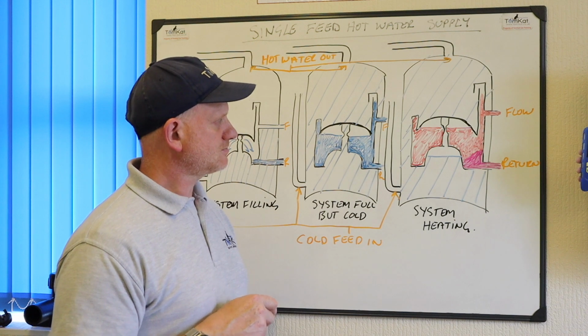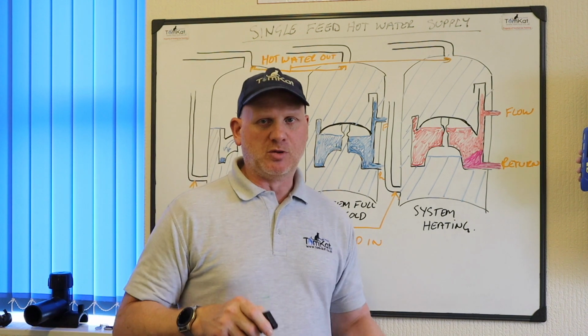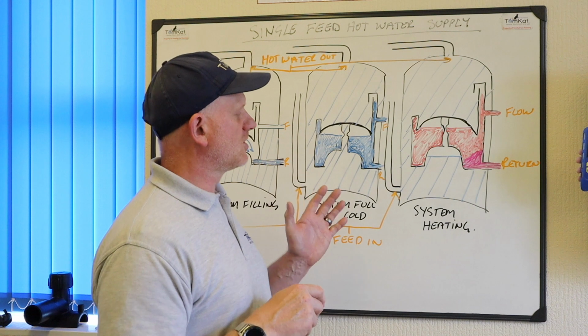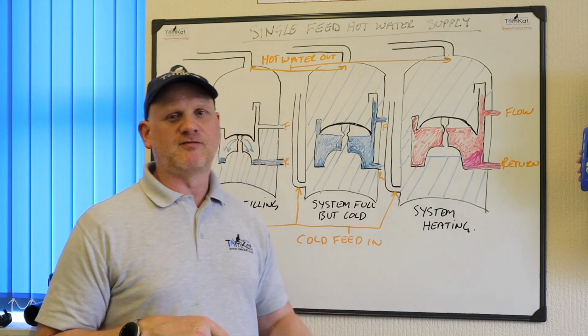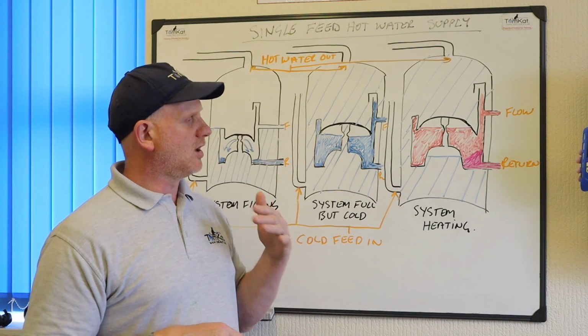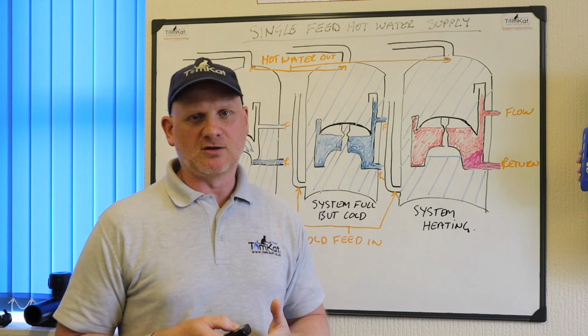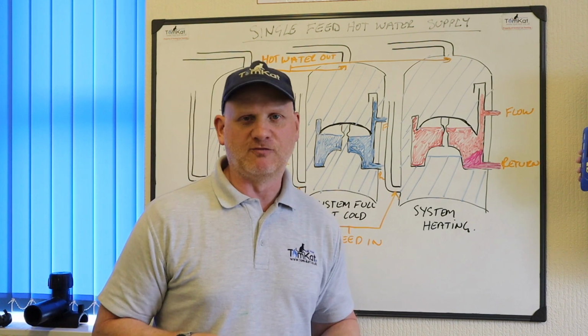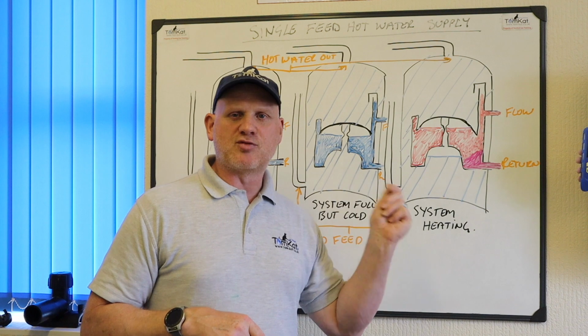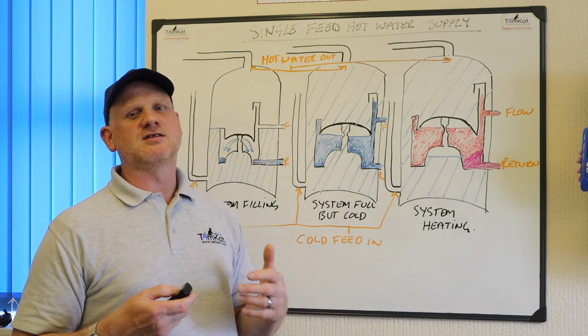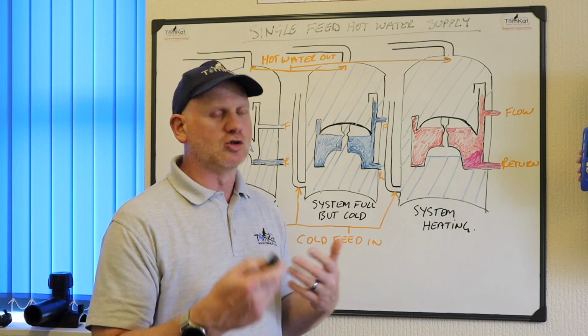Okay? So if you lose this bubble, what you've got to do is drain the cylinder and fill it back up again. Now what a lot of old plumbers used to do, so old guys like my old fella, if they had any problems with the primary flow and return, they used to take the thermostat out of the boiler and boil the water up.